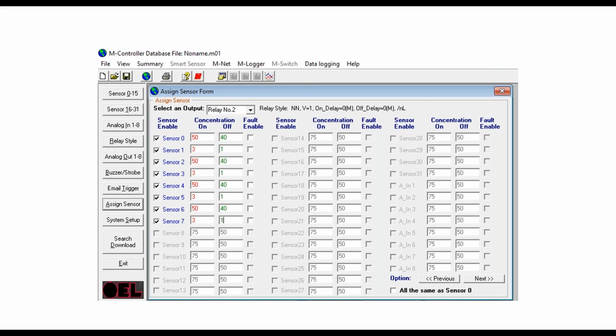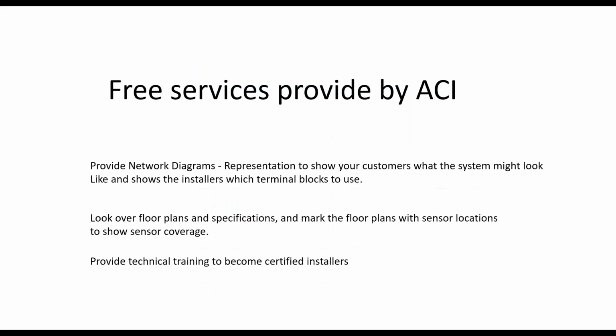This will be our second alarm level, or our high alarm level, and we'll make the concentration for CO on at 50, off at 40, and then for NO2 on at 3 and off at 1. Once we do that, all we do is download that into the M controller, and it's programmed. It's very, very easy to do.